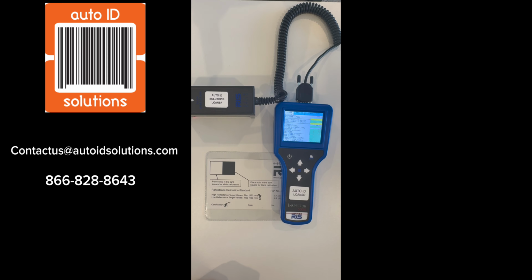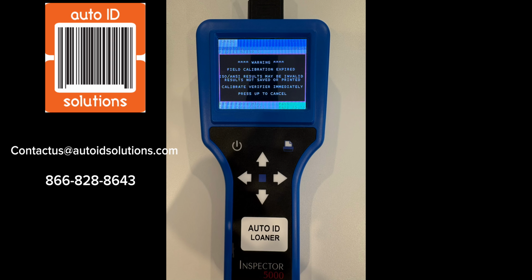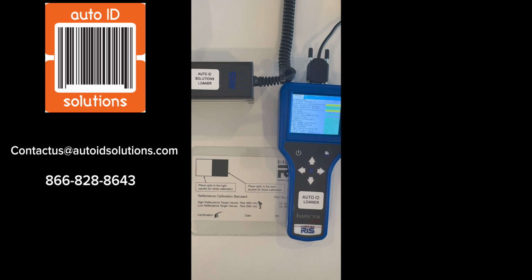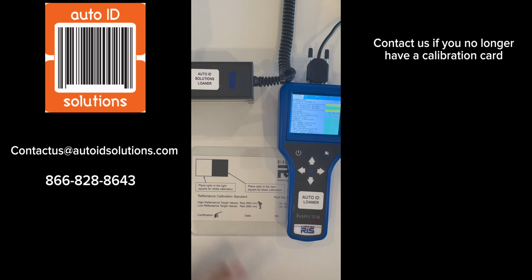There are two types of calibration for the i5000 Auto Optic. A field calibration should be completed every 2 to 3 weeks, depending on how dirty your environment is. You will see the following message when your verifier is overdue for field calibration. To field calibrate your i5000 Auto Optic unit, you will need the calibration card provided with your unit.